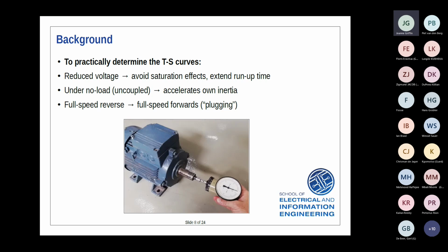Right, so what we do is we accelerate the machine to full speed in the reverse direction. Then we plug it by reversing 2 phases, which causes the machine to run through the braking region on the torque speed curve. So the machine decelerates quite quickly. It goes to standstill for a moment, and then it accelerates in a forwards direction to full speed. So the test is done from full speed reverse to full speed forwards, and we achieve this by plugging, reversing 2 phases, and that brings a slip of 2 to the circuit, so into the braking region on the torque speed curve.